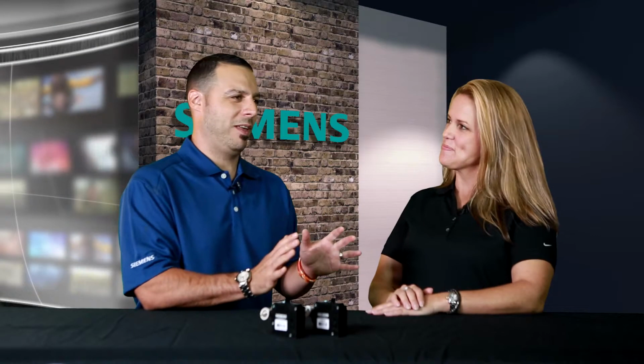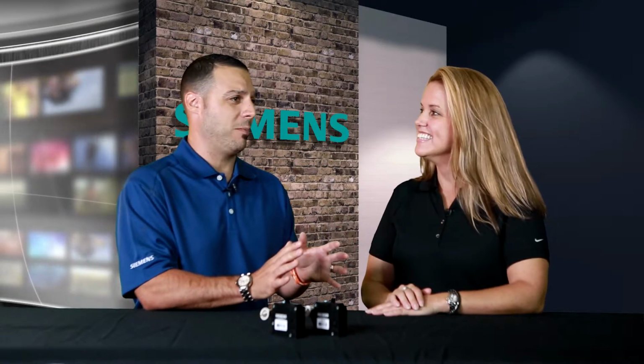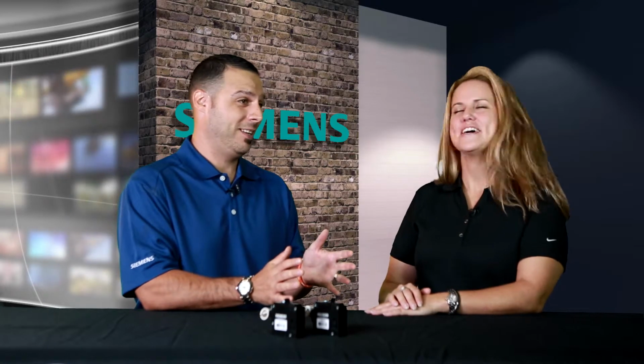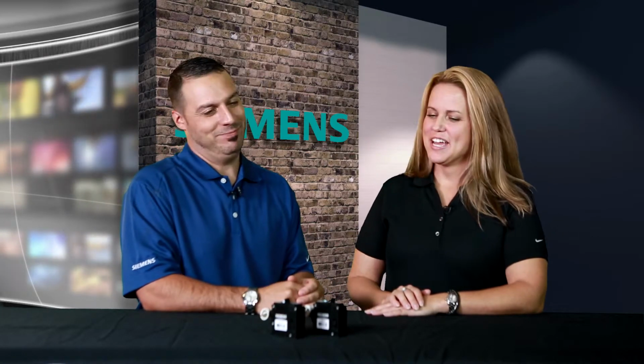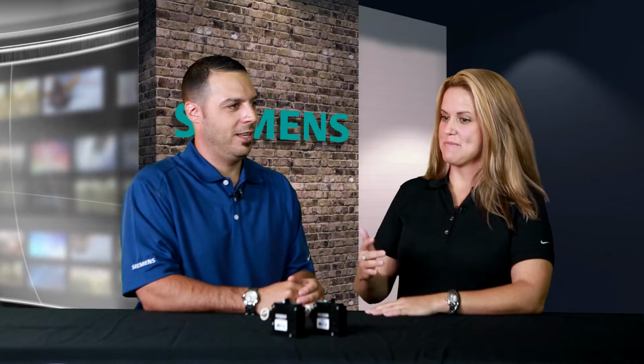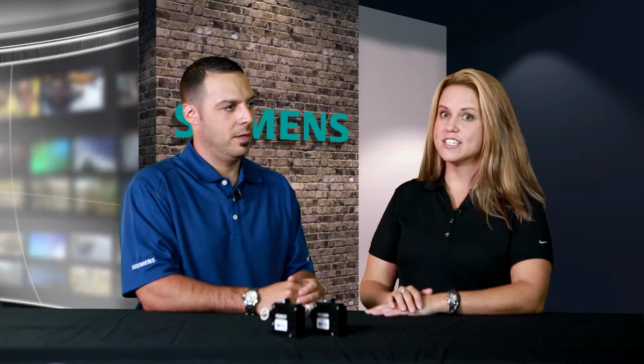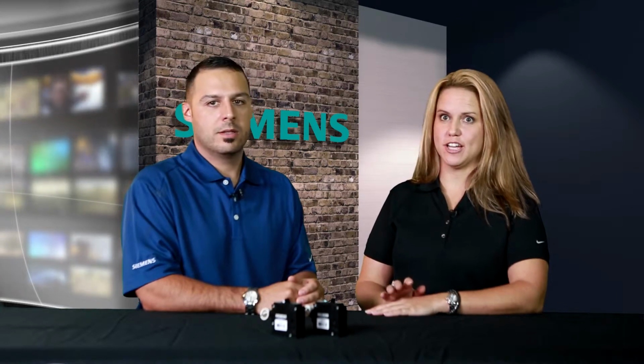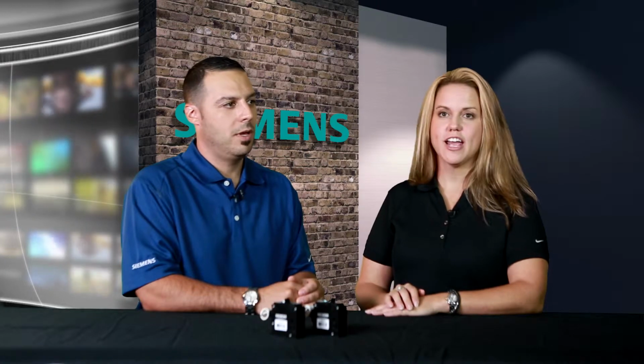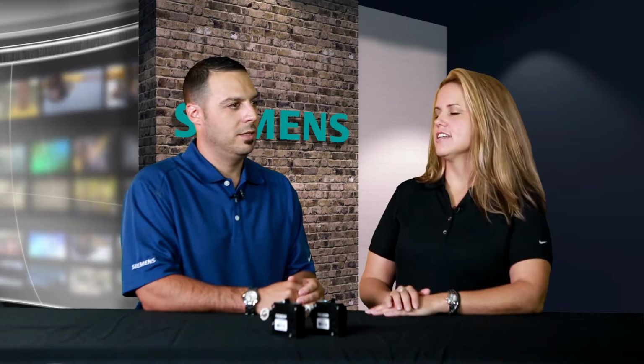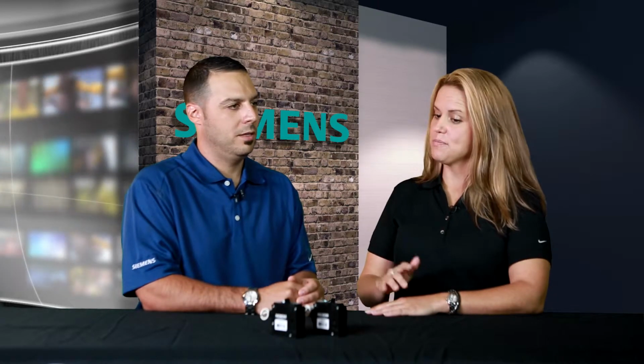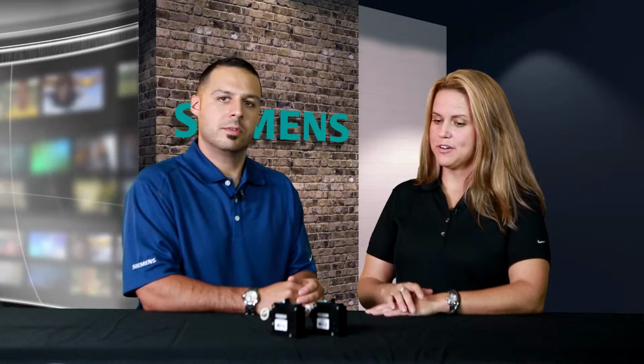Okay. UL actually suggests that homeowners monthly test their electronic breakers as well as their receptacles. You're telling me that a homeowner is supposed to test their breaker every month? Yes. And how often does that happen? I don't think that it does. Okay. So a UL requirement next summer will require the self-test and lockout feature in all electronic receptacles and breakers, and for GFCIs. So we have already put that feature into our breaker.